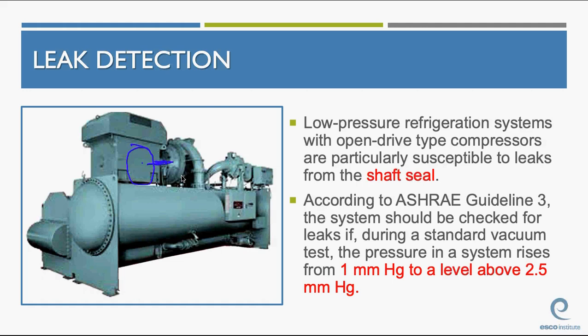According to ASHRAE Guideline 3, the system should be checked for leaks if, during a standard vacuum test, the pressure in a system rises from 1 millimeter mercury to a level above 2.5 millimeter mercury. Everything else we've done has been talking about inches of mercury. Type 3, you're talking about millimeters of mercury. Just be very aware of that, because they're going to do that on a multiple choice question. Type 3 is the only one we've been talking about millimeters of mercury.